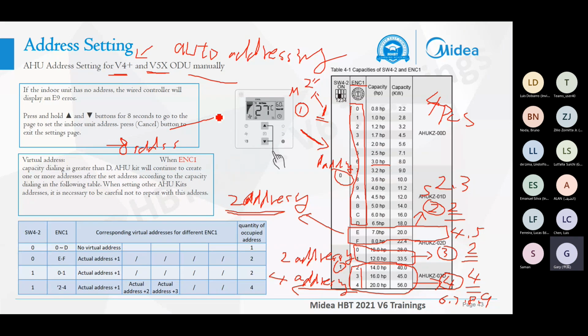So you check the wired controller. You will find there are 8 indoor units. But actually you only have 4 kits. But the wired controller will show that you have 8 indoor units, as the wired controller thinks each number is 1 indoor unit. So this is the very important part. So remember, set the right address for each AHU kit. This is for the old generation VRF, as this VRF didn't have the auto addressing function. So the addressing setting of the AHU kit is somewhat complex.